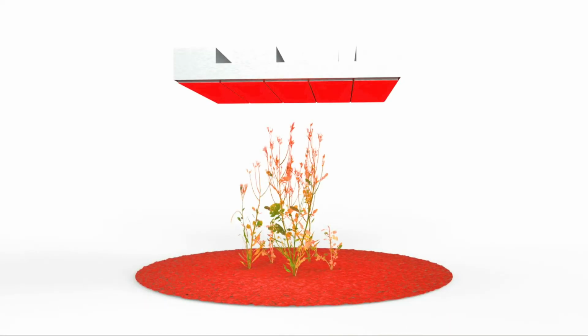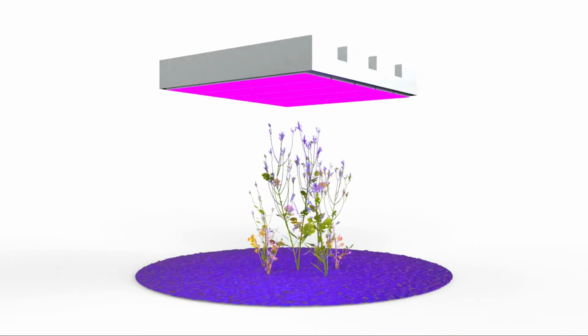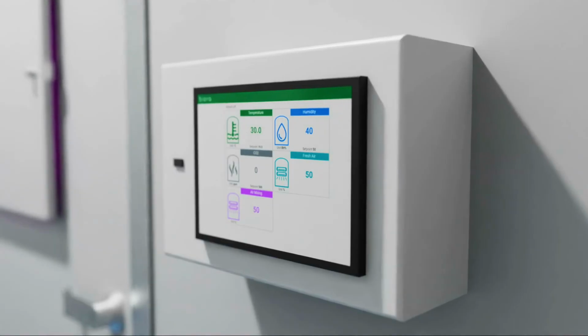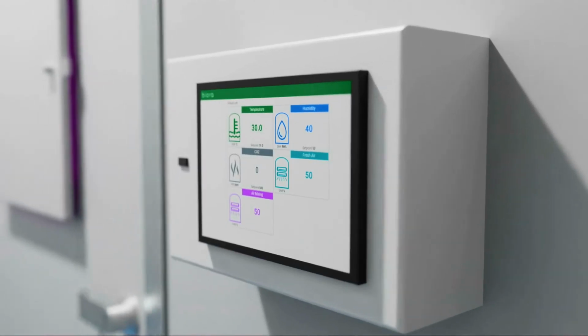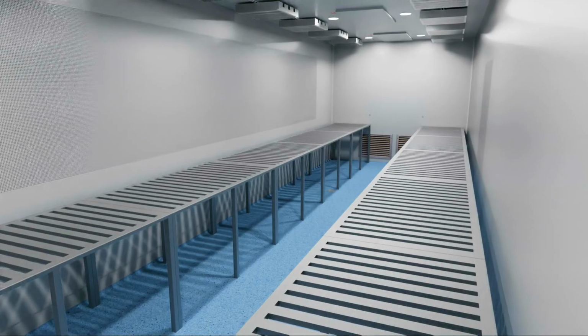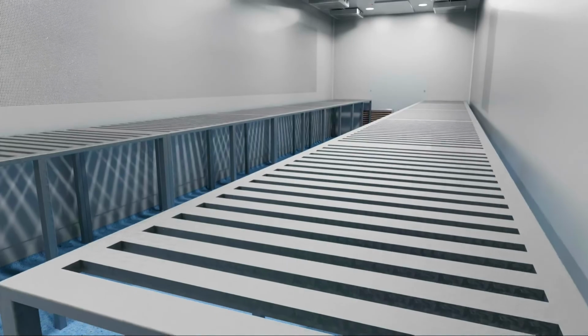As the primary light source, the chamber is fitted with high-intensity broad-spectrum LEDs that are dimmable. While different light options suit different applications, these lights are designed to mirror natural conditions plants experience outside. Lights of varying spectrums and intensity are optional for specific vegetation and flowering conditions. Each bank of lights can be run independently through the HMI. The chamber is equipped with general lighting used when grow lights are off or during maintenance.